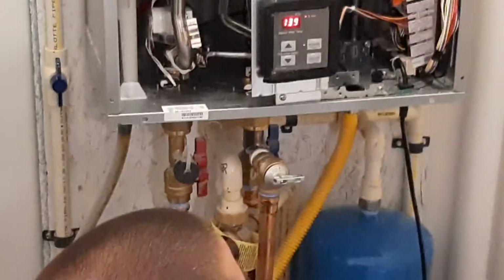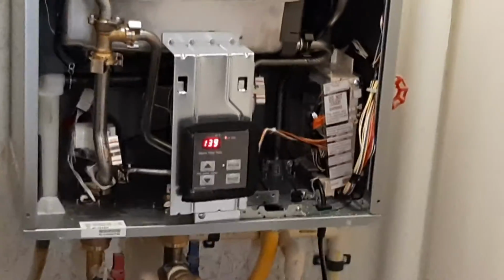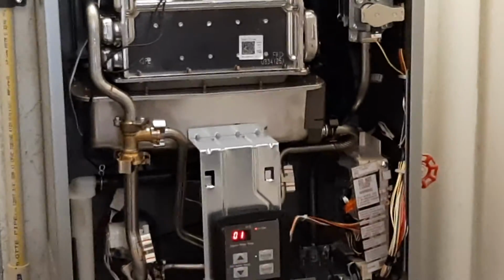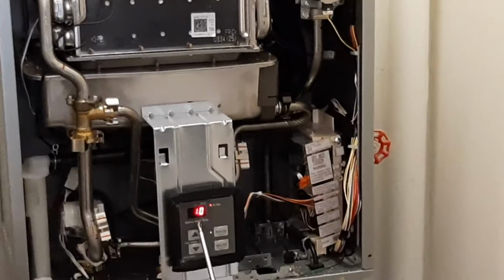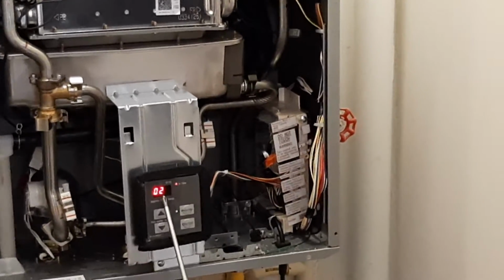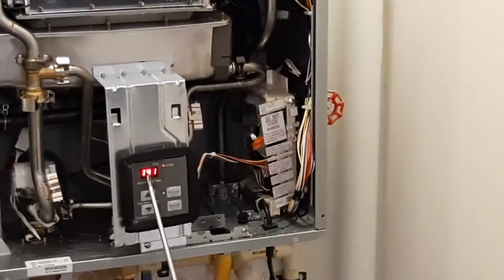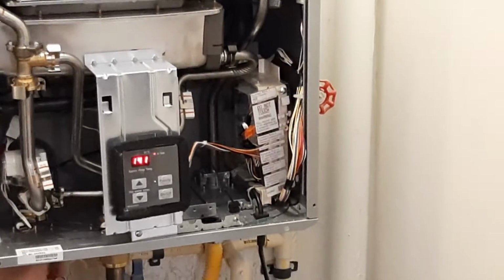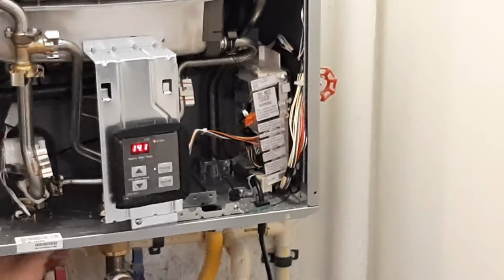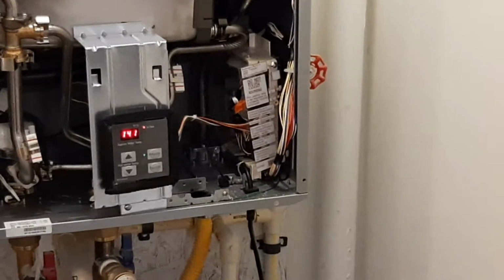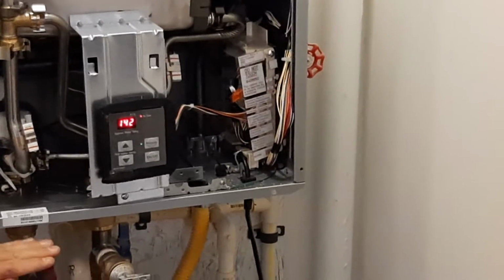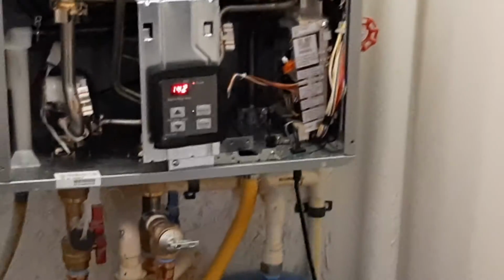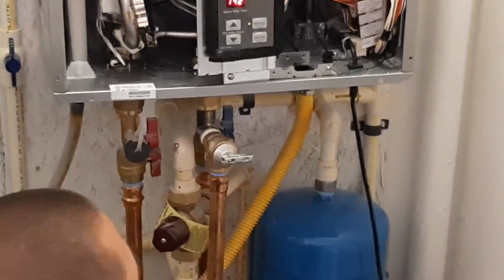So that's an easy, if the homeowner says I don't have hot water at my faucet, this is kind of the first thing to check. Do I have flow? Yes. Do I have hot water leaving the unit? Yes. And so that says 140. 140 is pretty hot, but I can grab it quickly. That's absolutely hot water. So if they didn't have hot water at their faucet, I would know it's a problem outside of the water heater, from here down. And it normally would be the mixing valve.